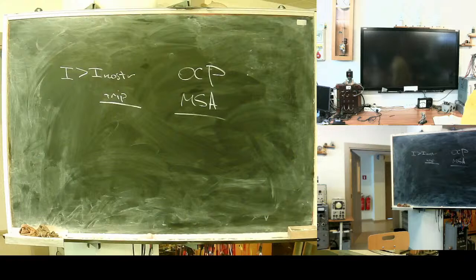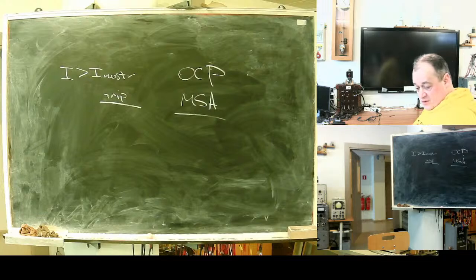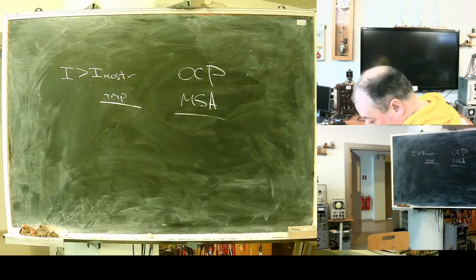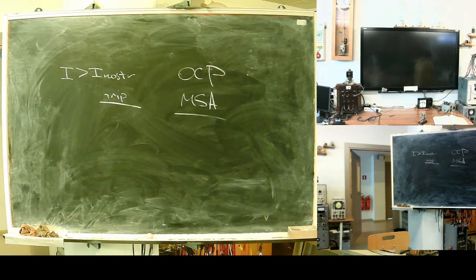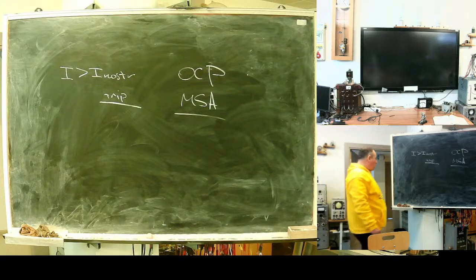So all overcurrent protections disconnect the line, or, I don't know, it can be a transformer protection or something, if the current is above the threshold. Good threshold. To set a threshold, you need to perform fault modeling. This allows you to say: okay, now I see for this one 100 A is normal, 120 is suspicious, but 200 is definitely a fault. So if the current is above 200, I disconnect. I send a disconnection signal. Okay, 200, 2000 maybe. Anyway, if the current is above, I disconnect. Overcurrent protection.